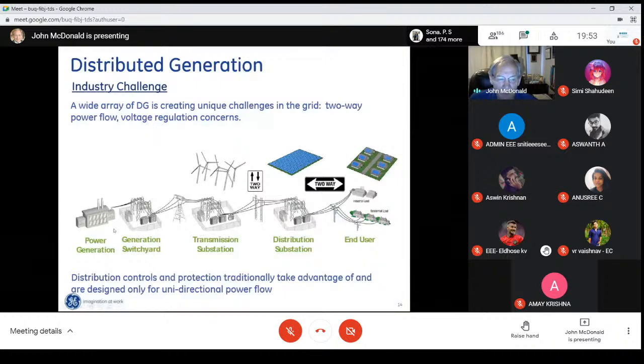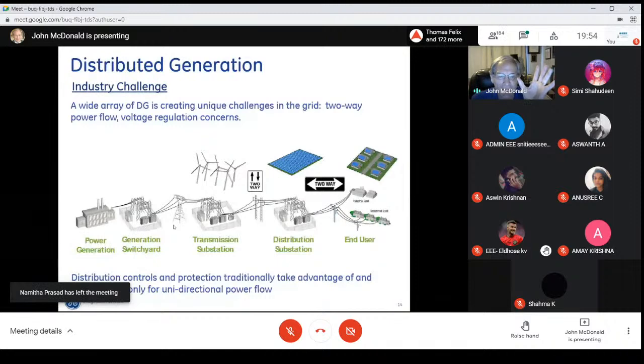So, if you look at the grid from generation, the switch yard right outside the power plant, right? That's where we step the voltage up. As you know, we can generate at say 11,000 volts, but to transmit the electricity, we have to raise the voltage substantially to minimize the losses, right? Remember, power is voltage times current, but losses are a function of the square of the current. So power is voltage times current. If we can raise the voltage substantially to send that same amount of power, we can do it with a lot lower current, right? E times I, raise E, lower I, and losses are a function of I squared. So it greatly reduces the losses.